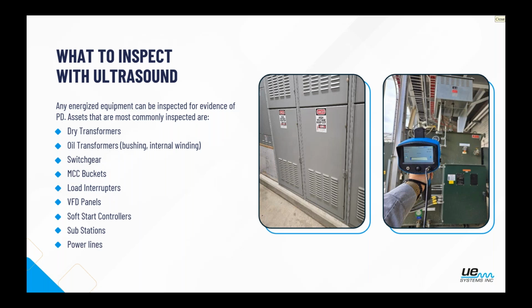All right, so now that we've covered the foundations, what we're looking for as far as making a good inspection, mistakes to avoid, typically when we're using ultrasound, there are specific assets that we're looking for. As I said earlier, always needs to be energized, but typically the most common inspected piece of equipment are going to be dry transformers. Once again, the voltage is not a big concern except for the reporting side of it, so we can inspect medium, low, and high voltage.